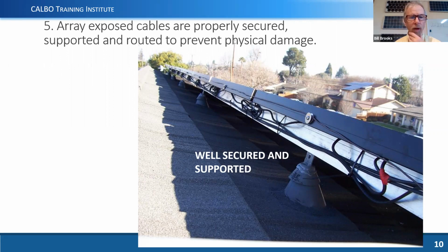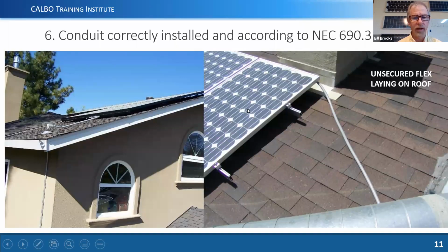Here's an example where the cables were all supported up at the top and not hanging down. They're accessible if somebody needs to test a module. This was a nice, cleanly installed system. Maybe their grounding hardware wasn't quite right, but we'll not go there at the moment. You can see across the street there's another PV system, and there are several on that street because they were done neatly, and so many of the neighbors decided they wanted to go for it as well when they heard how good that customer's electric bill was. So, correctly installed conduit on the roof. Here you have a piece of flex just laying on the roof. That's not acceptable. It has to be properly secured and supported.